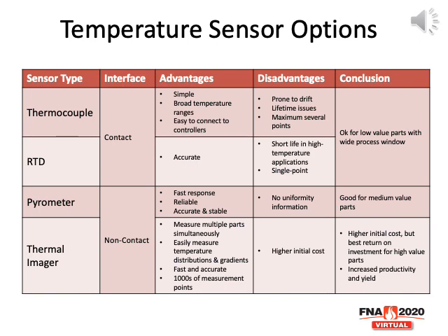The thermocouples and RTDs, especially for high temperature furnaces, are limited in that they're a point contact. You can't put them everywhere, or not in a cost-effective way. And especially for higher temperature processes, they're quite prone to failure and drift over time and just surviving in the environment. So they're certainly appropriate for low value applications, or maybe a couple of points in a very challenging application as kind of a reference.